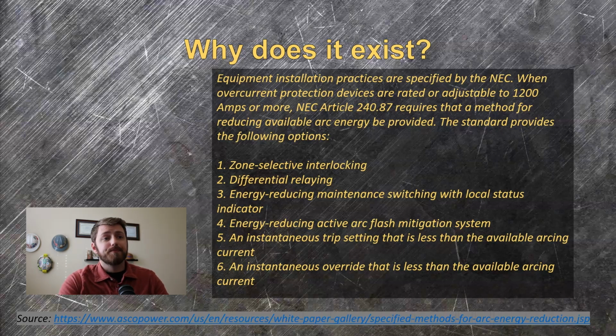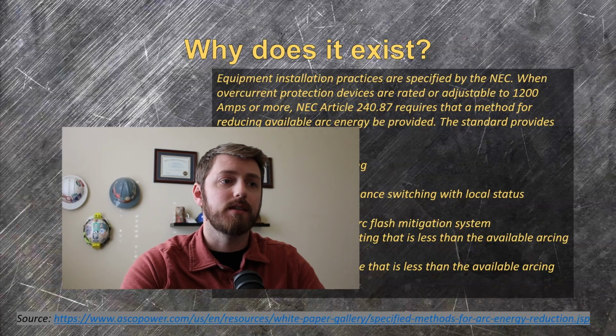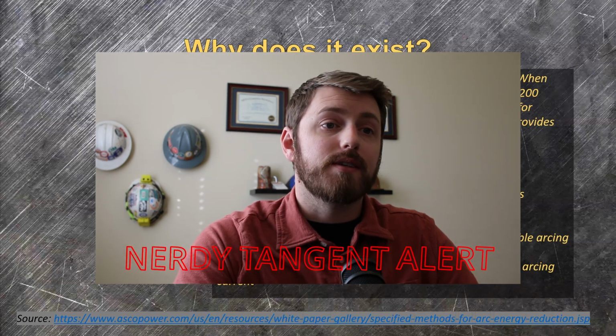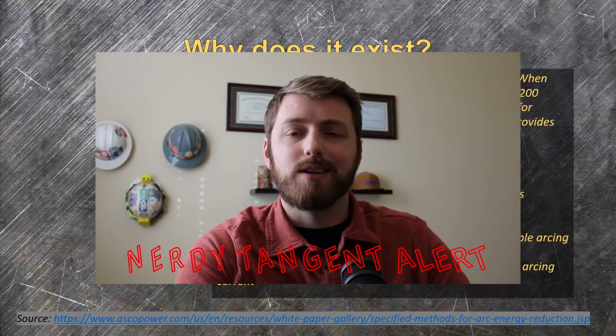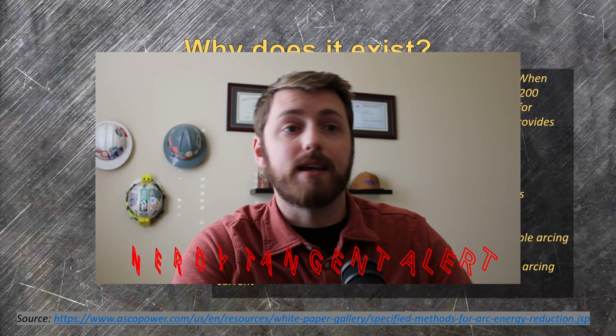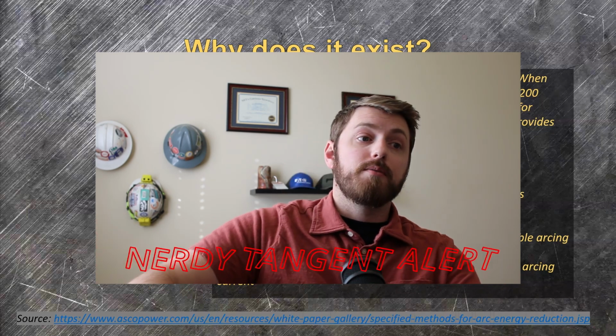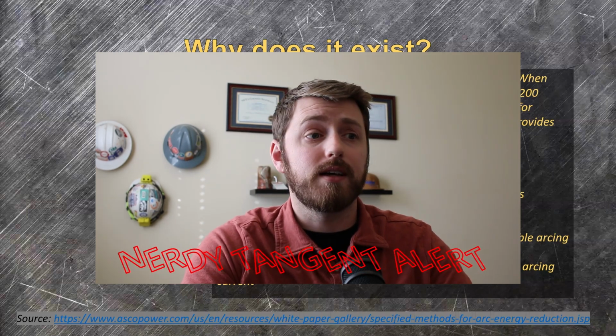Without getting too far in the weeds, if a power system is nominally rated 1200 amps or higher and the instantaneous rating of the breaker can't be set below the system's arcing current, one of these methods needs to be implemented. A bit of a tangent: the arcing current here is a calculated theoretical value of fault current which the system would need to maintain in order for an arc to be self-sustaining, and thus dangerous in the event of an arc flash. I'm no engineer, so take this with a grain of salt, but the arcing fault current is typically like 40% of the bolted fault current and depends heavily on the impedance of a system and the size of a transformer that feeds it.